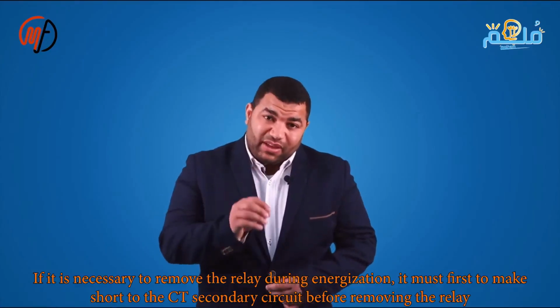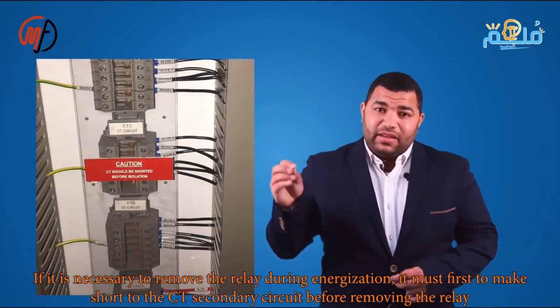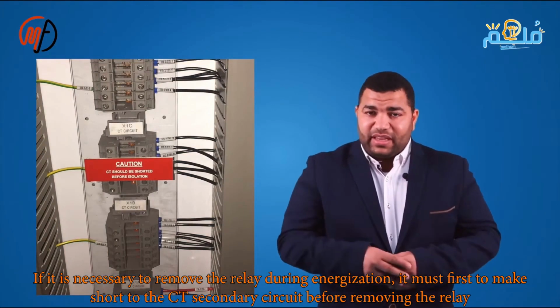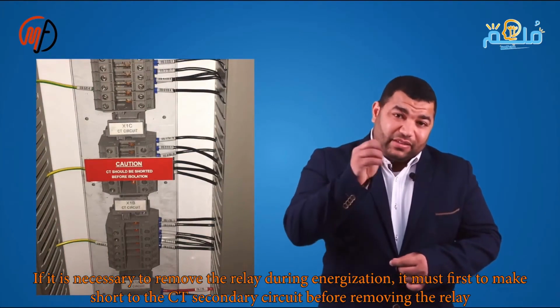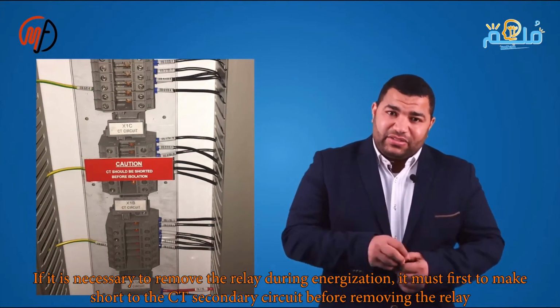If removing the relay, short the CT secondary terminals first. This keeps current flowing, opposes the primary MMF, and prevents voltage rise. VT is parallel, CT is series.